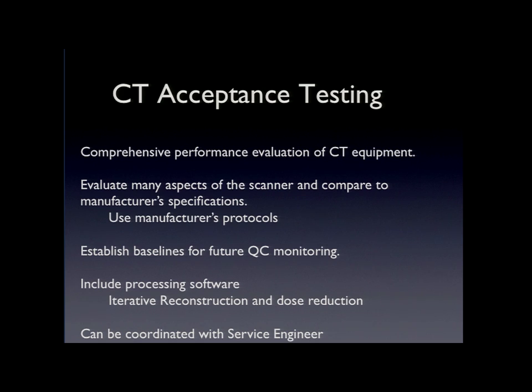At that time, you also establish standards and baselines for doing the QC. So we'll set that up and work with the technologists. Also, there are all these protocols, reconstruction algorithms, and software supposed to help minimize dose, so you would include evaluations to see if that is really happening. That can be coordinated with the service engineer because they're there doing it and supposedly setting it up to meet those standards. So it's good if you can coordinate that effort together.